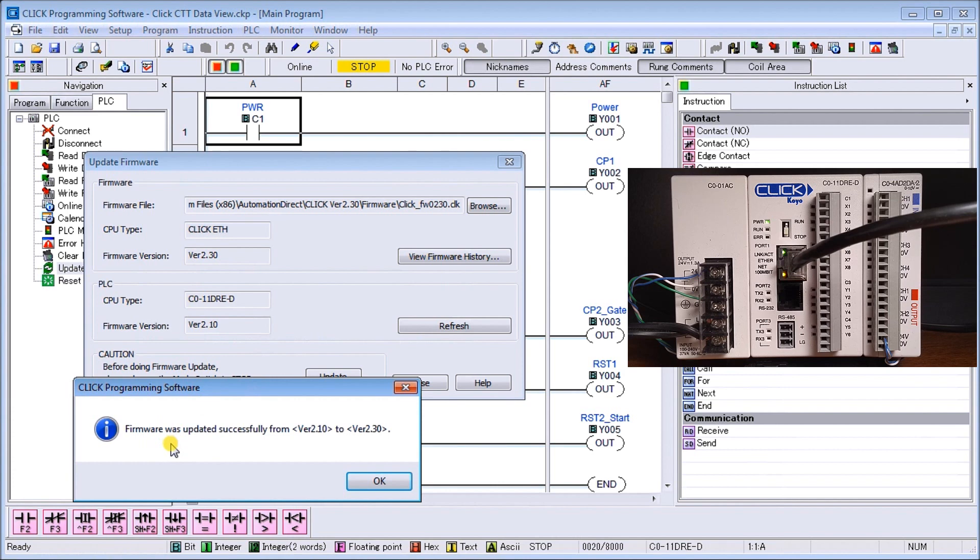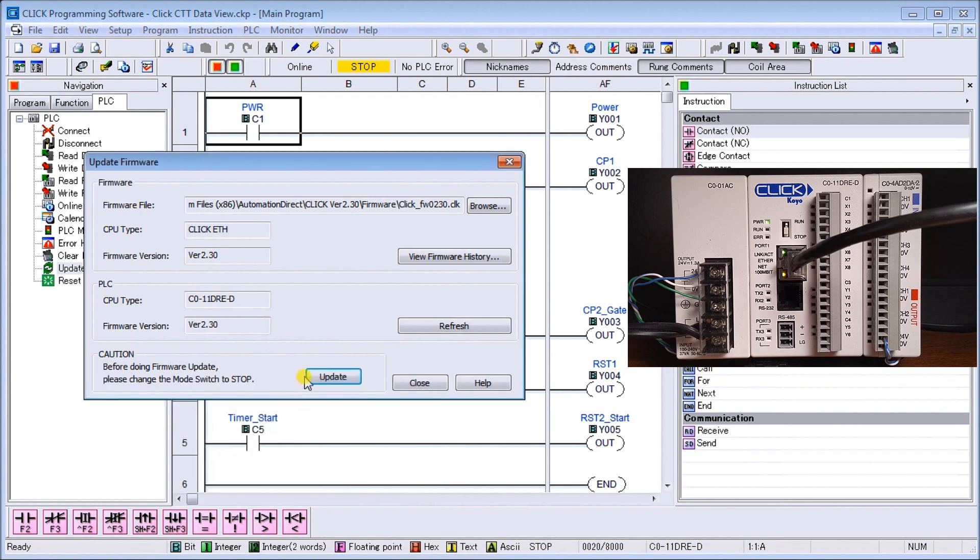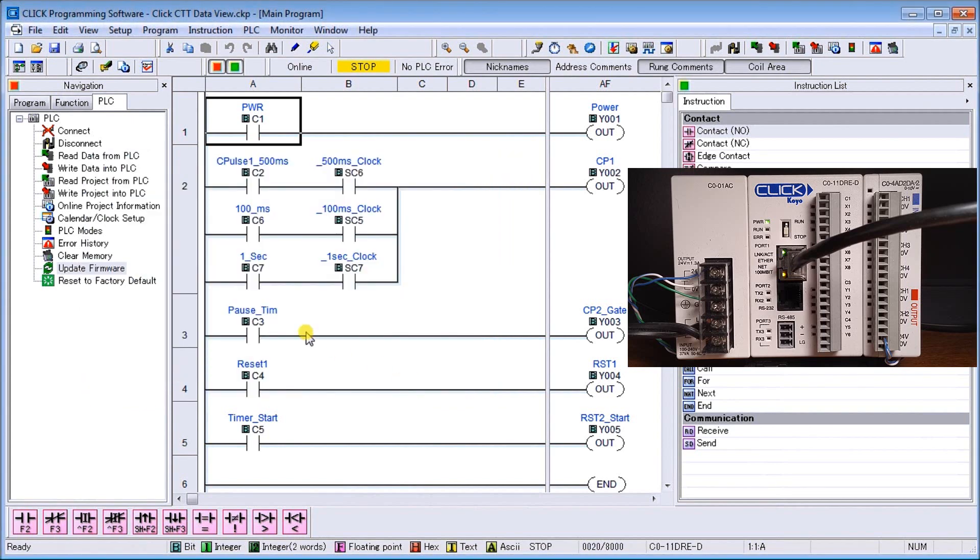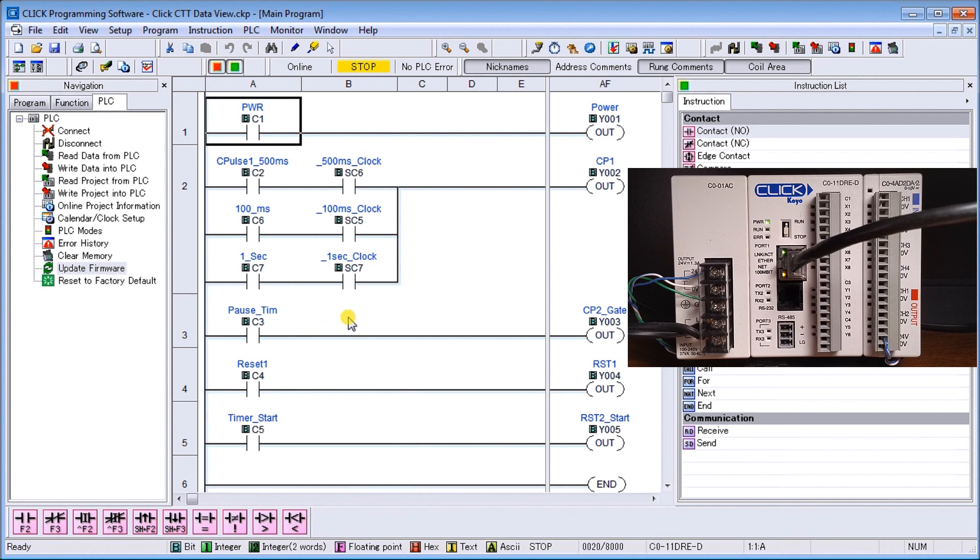Now we have a message that firmware was updated successfully from version 2.10 to version 2.30. We'll hit okay. Here's our PLC now at version 2.3 and our program at 2.30. We'll hit close. Now our version and our CPU is the exact same. That's all there is to it and we've kept our existing program intact. We can go back and run this program once again.